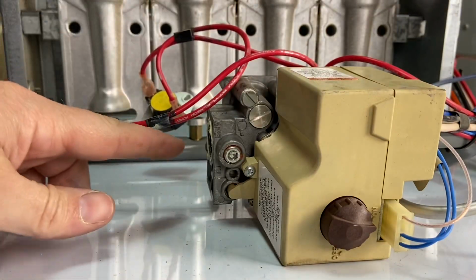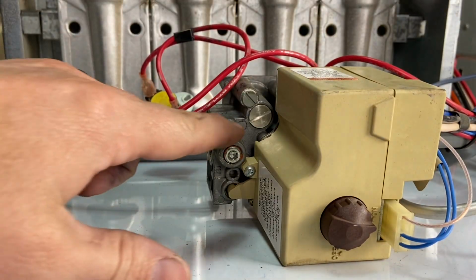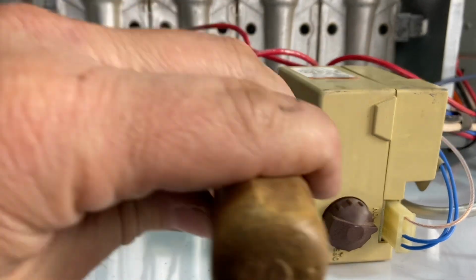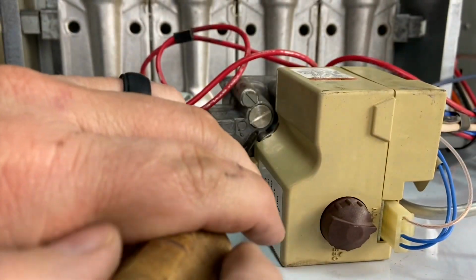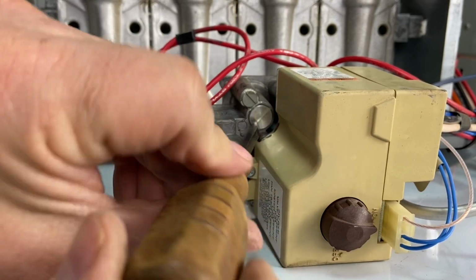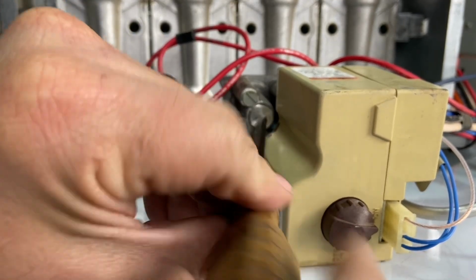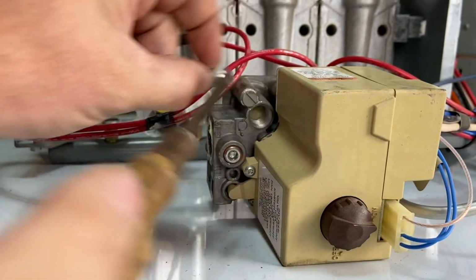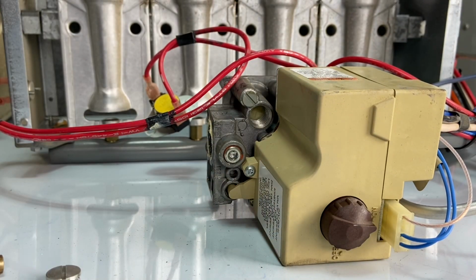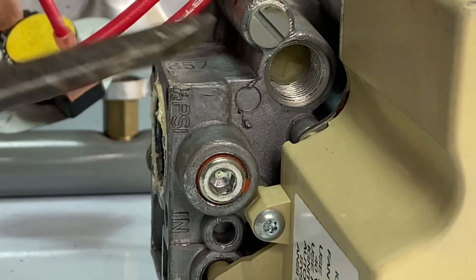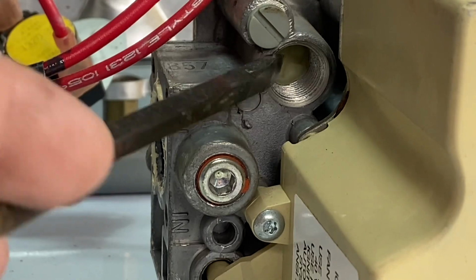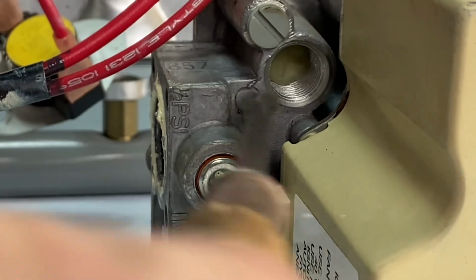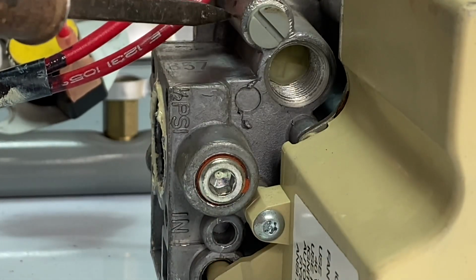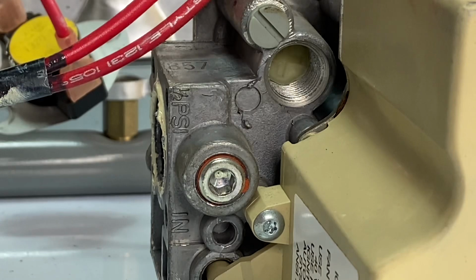On this side here is our incoming, where a gas line would come into this. And right here, you see this little shiny port. If I use my screwdriver here, we could unscrew this port, and this allows us to get to our adjustment for our gas pressure. Remember, this is a combination gas valve, a combination of a gas valve and a pressure regulator. If we zoom in here, you can see this component right here is what we'd use to adjust the gas pressure. You would put it in that plastic piece, and if you screwed it in, it would increase gas pressure, and if you backed it out, it would decrease the gas pressure.